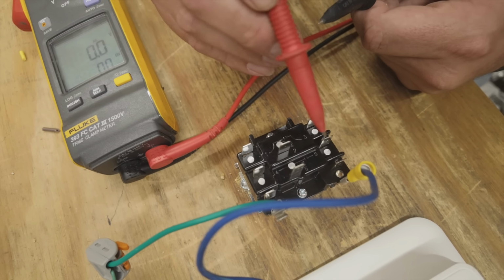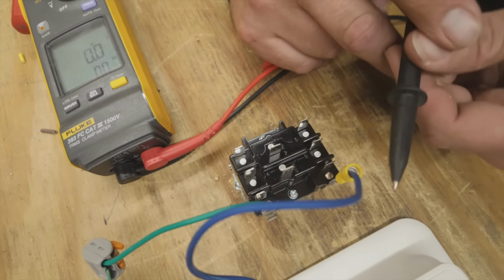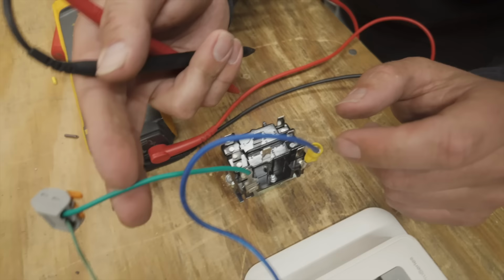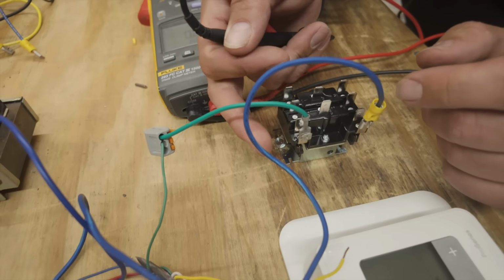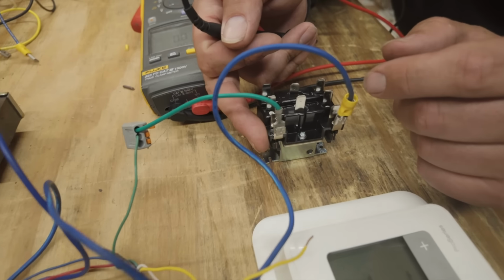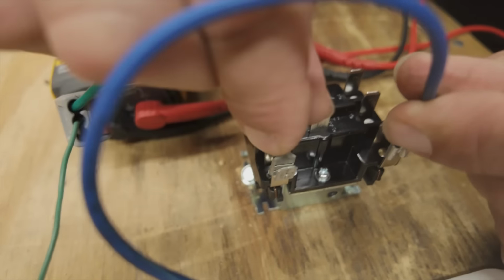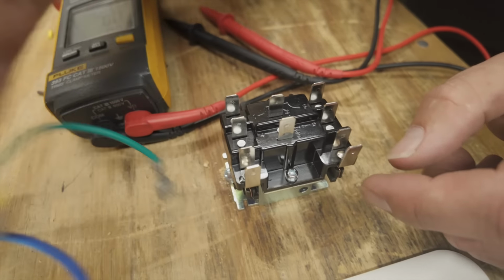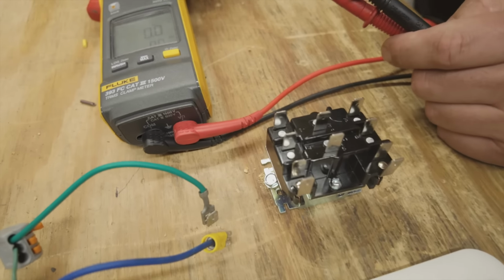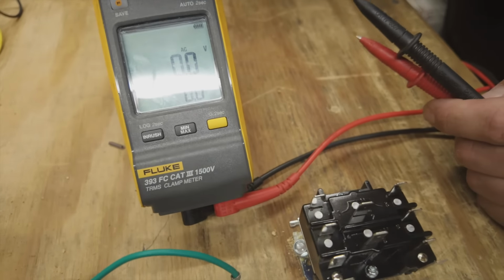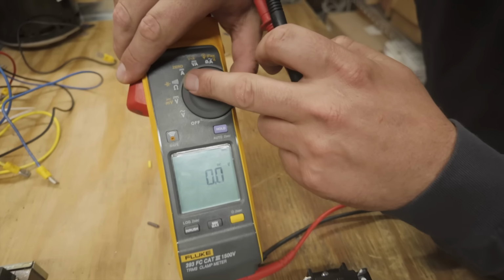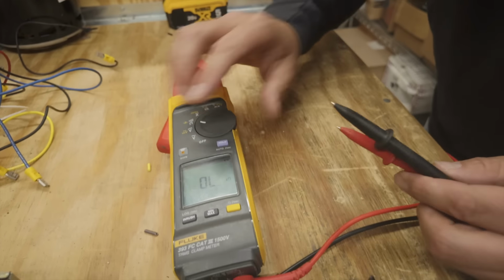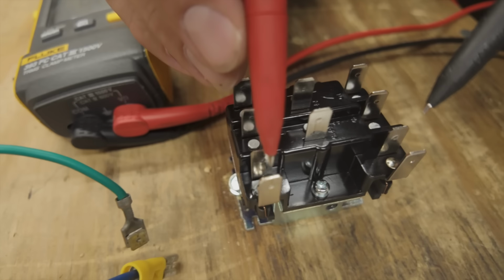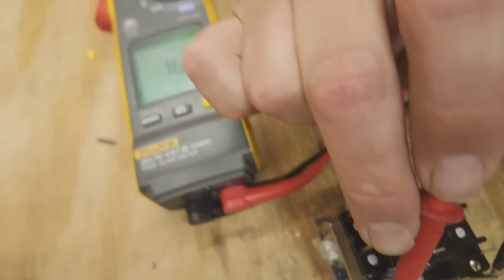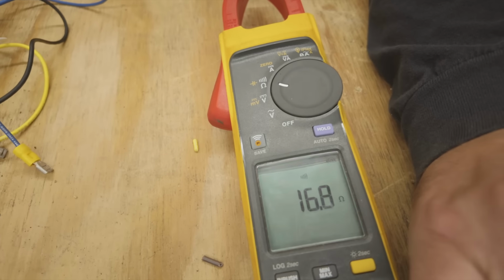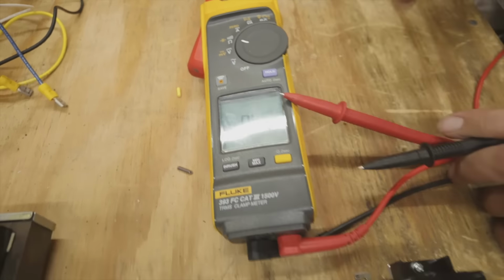4 to 6 will close, all right? So I'm going to show you that. I've got the green wire now hooked to one side of the coil. This is the coil, okay? If I take these wires off, I should have showed you that with the contactor. Whenever I take these wires off, if I put my meter to ohms, I go up here to the upside down U, and I go to the coil, you see the reading I get? 16 ohms. That's a good coil.